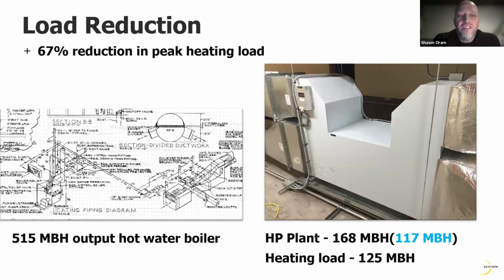I mentioned load reduction. The existing boiler was a 515 MBH output hot water boiler. What replaced it was a heat pump of 168 MBH. So that's a pretty significant reduction, really attacking the load. It's about 800 square feet per ton, for those who are dialed into sizing on heat pumps or general heating load. The 117 listed in the parentheses is the derate condition. The heating load came out to about 125, and so we sized just a slight bit less than the design heat load, but we haven't had issues.